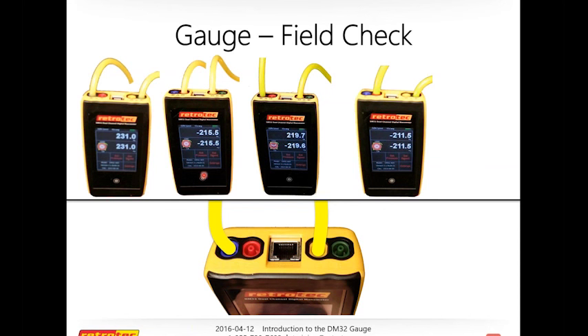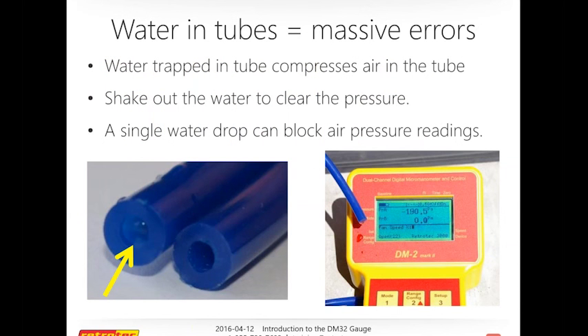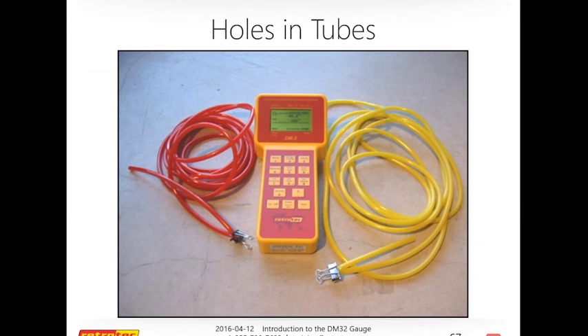Another thing to make sure of is simple things like there's not water in your tubing and there are no holes in your tubing. Here's another test that you can do. Here we have this tubing plugged in to a DM2. Then I've clipped off the top to create a pressure inside of it, and then I watch the pressure. If that pressure depletes rapidly, then I know that there's a hole in that tube.